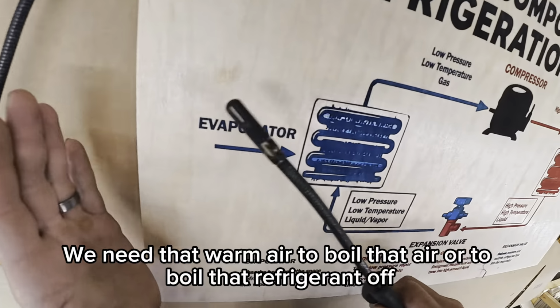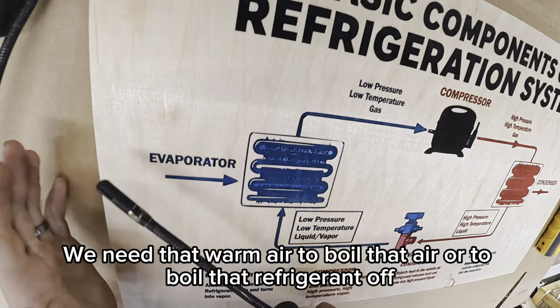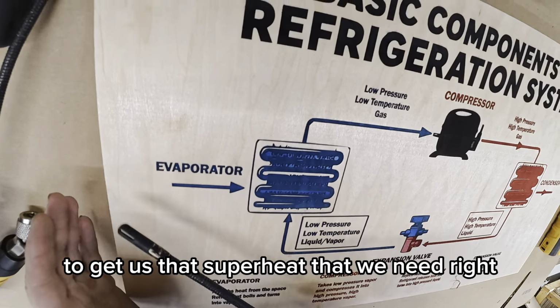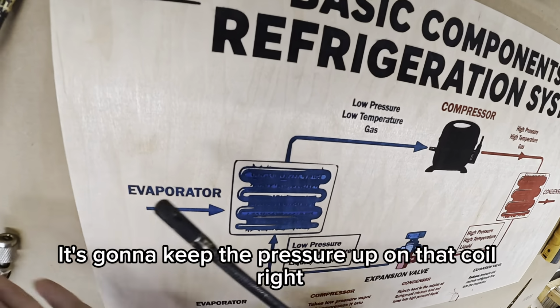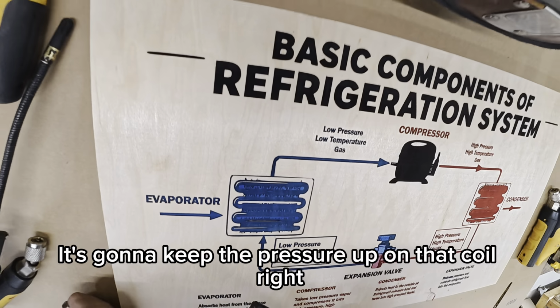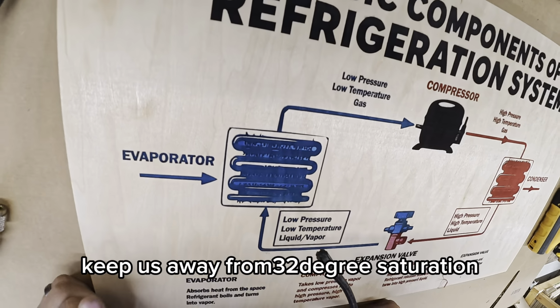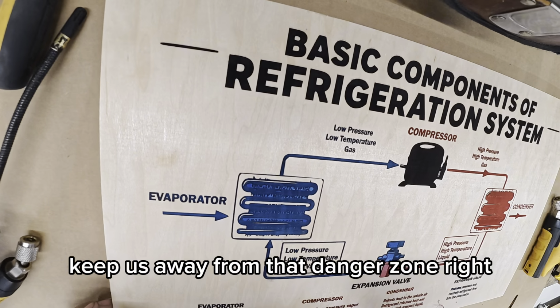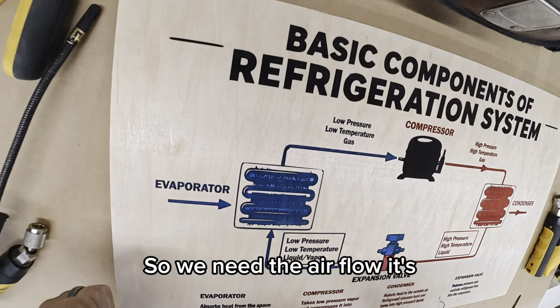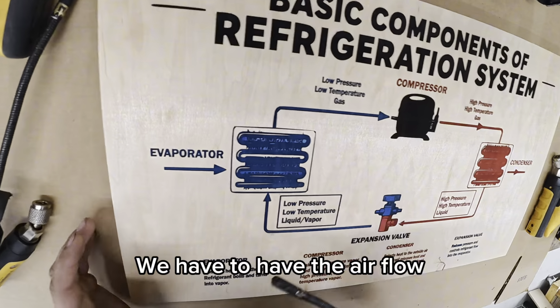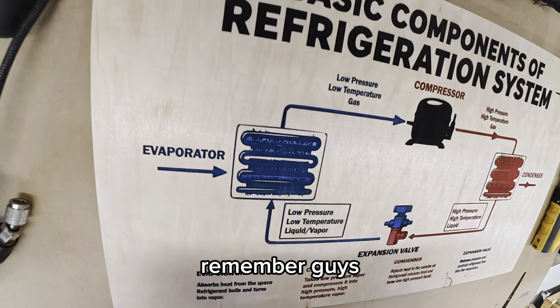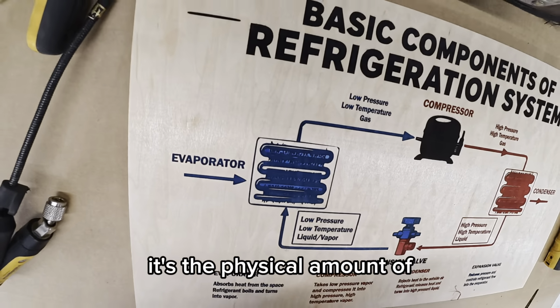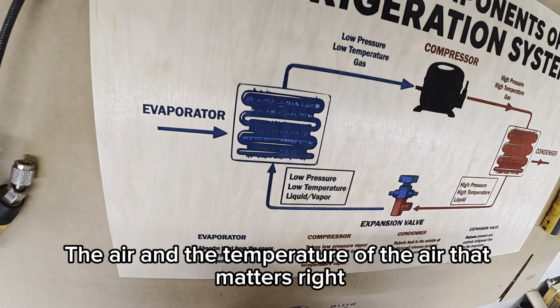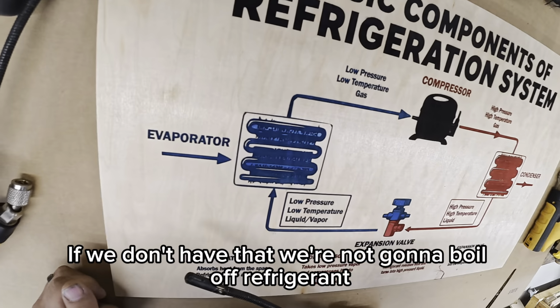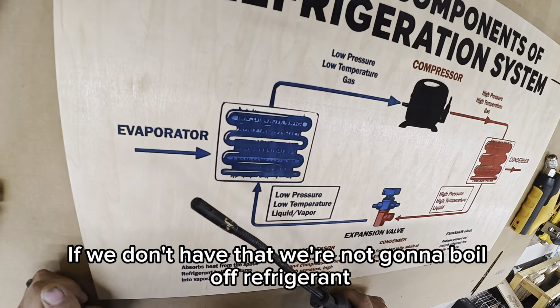We need that warm air to boil that refrigerant off, to get us that superheat that we need, right? Otherwise it's gonna keep the pressure up on that coil. Keep us away from 32 degree saturation. Keep us away from that danger zone, right? So we need the airflow. It's very important. So remember guys, it's the physical amount of the air and the temperature of the air that matters. If we don't have that, we're not gonna boil off refrigerant, right?